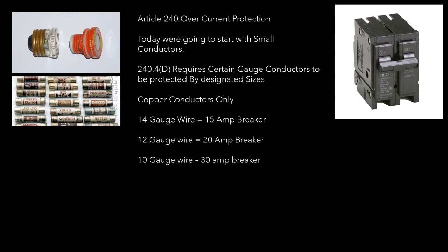12 gauge wire is limited to a 20 amp breaker. A 10 gauge wire is limited to a 30 amp breaker.